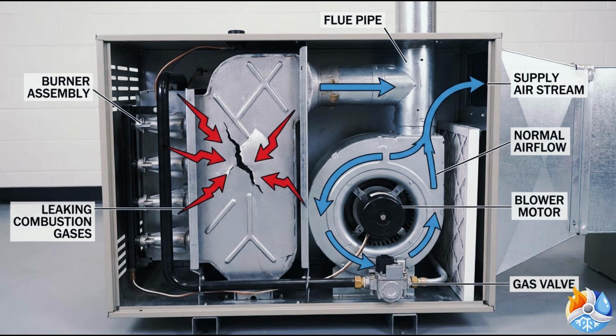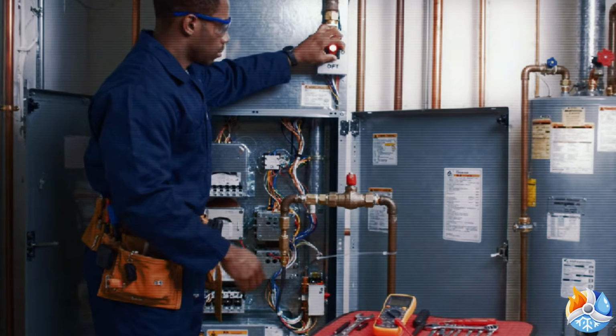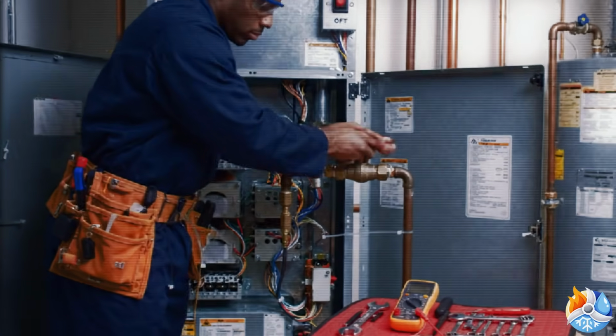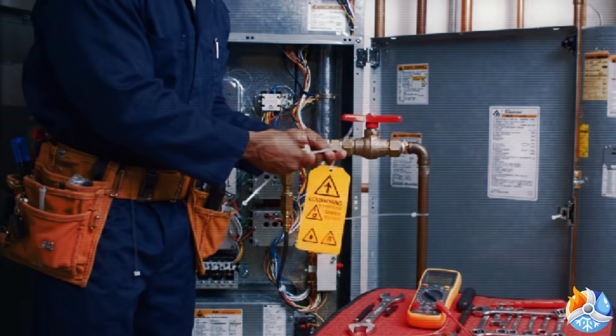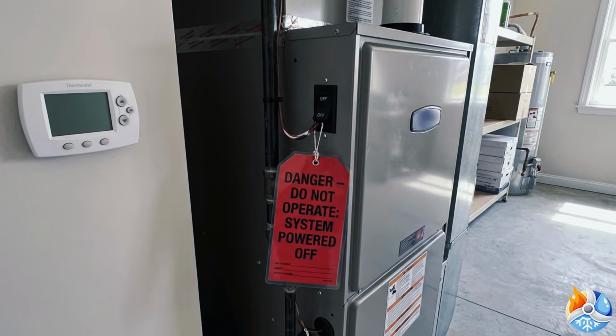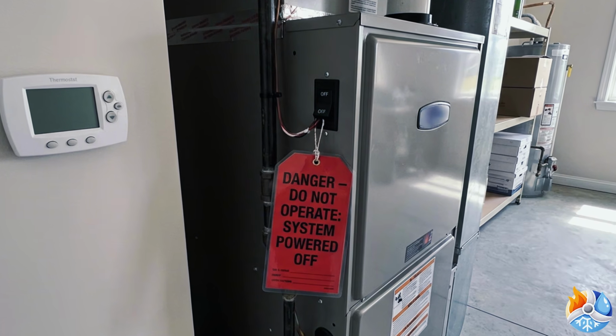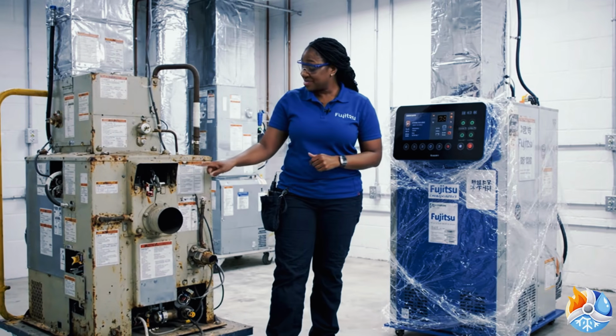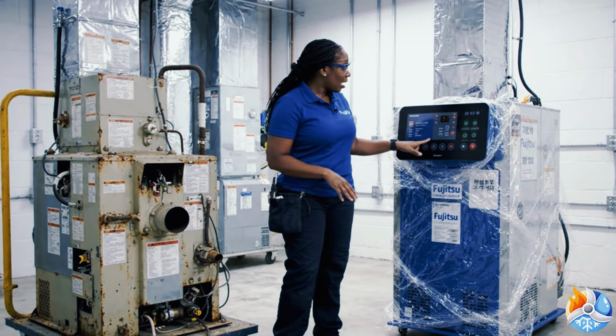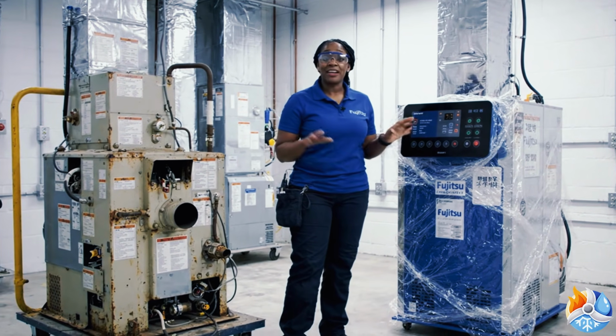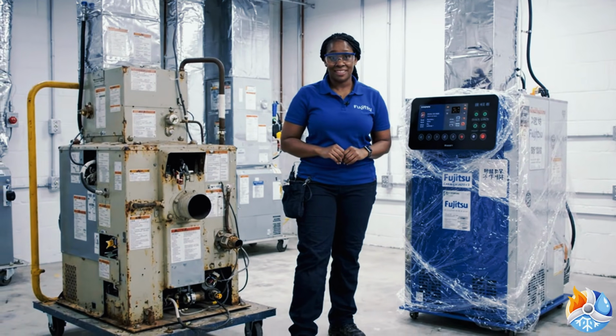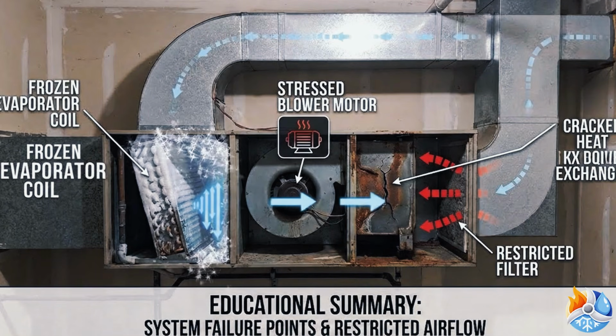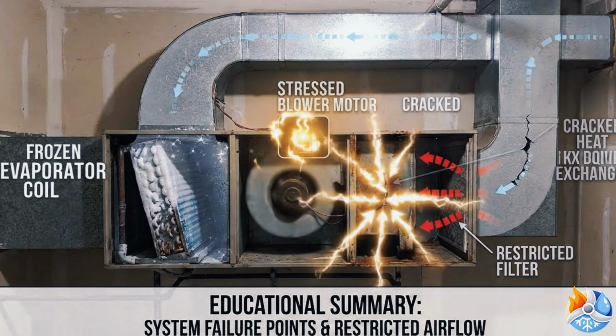A cracked heat exchanger means combustion gases, including carbon monoxide, can leak directly into your living space. Any certified technician who finds a cracked heat exchanger is required to shut your furnace down on the spot. You cannot use it until it is repaired. Replacement can run into the thousands. In many cases, the technician will recommend replacing the entire furnace, anywhere from $4,000 to $7,000. All three of these failure modes share one common thread: restricted airflow.